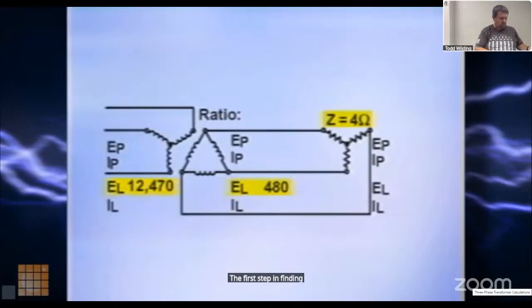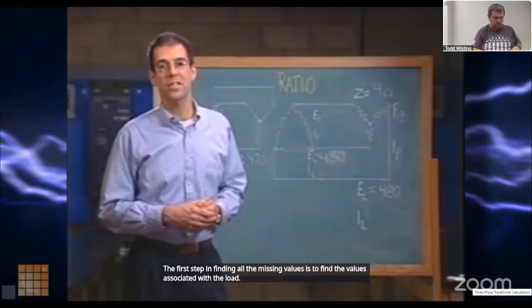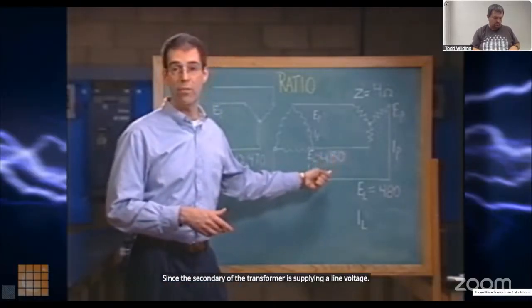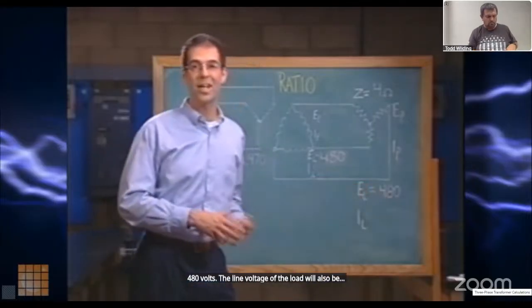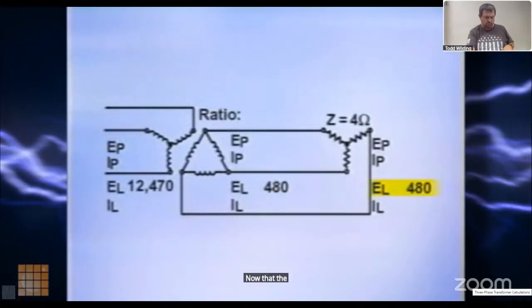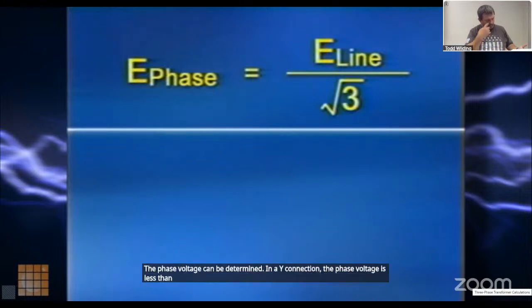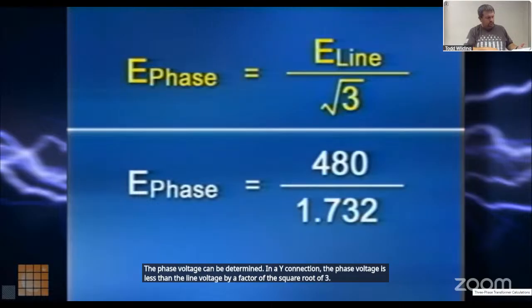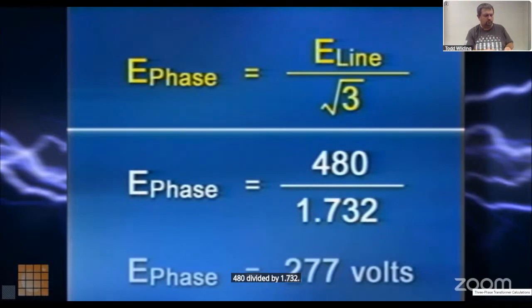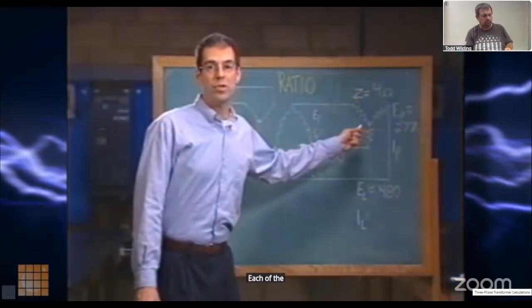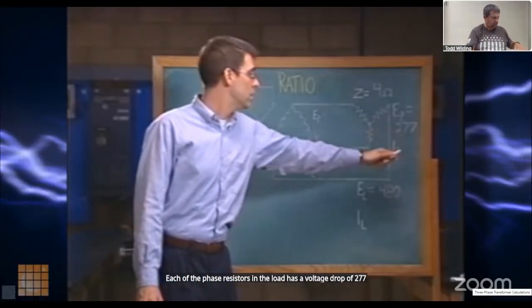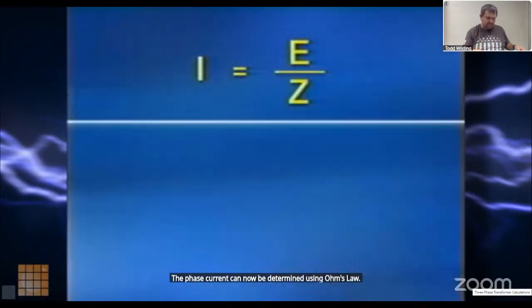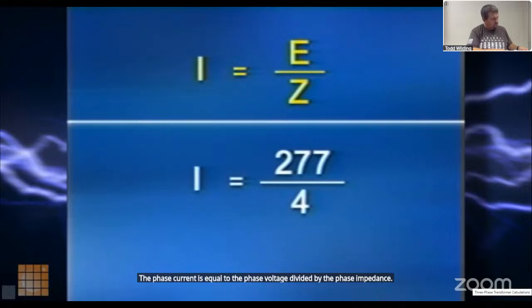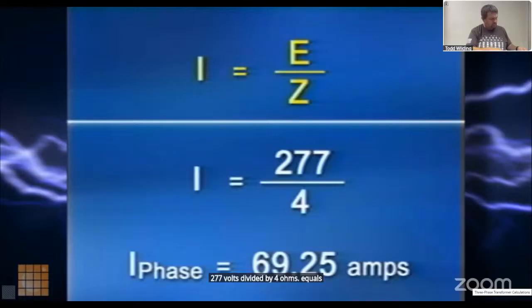The first step in finding all the missing values is to find the values associated with the load. Since the secondary of the transformer is supplying a line voltage of 480 volts, the line voltage of the load will also be 480 volts. Now that the line voltage connected to the load is known, the phase voltage can be determined. In a Y connection, the phase voltage is less than the line voltage by a factor of the square root of 3. 480 divided by 1.732 equals 277 volts. Each of the phase resistors in the load has a voltage drop of 277 volts. The phase current can now be determined using Ohm's law. The phase current is equal to the phase voltage divided by the phase impedance. 277 volts divided by 4 ohms equals 69.25 amps.